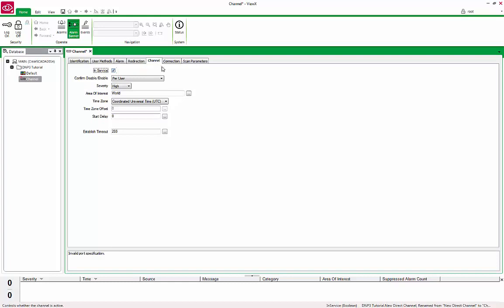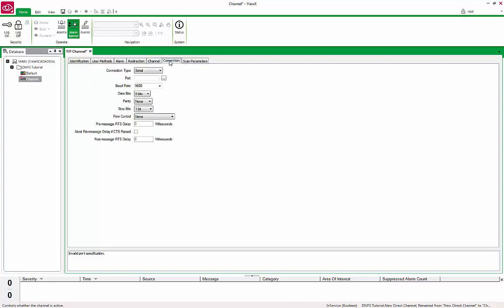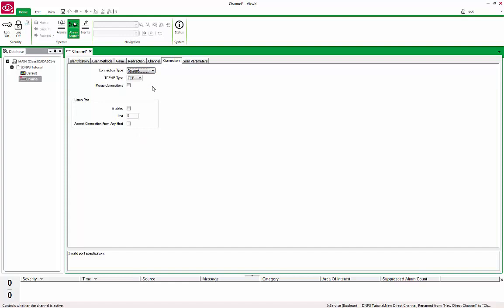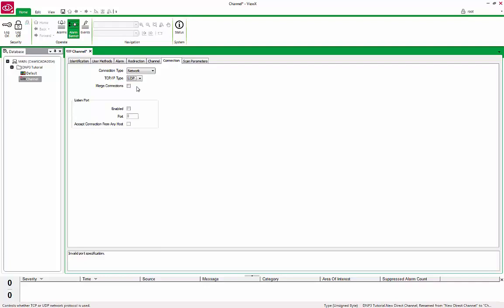Go to the Connection tab and change the Connection Type to Network and the TCP IP Type to UDP. You may need to change this part of the configuration depending on the setup of your DNP3 device. To allow your DNP3 device to send unsolicited message or report by exception, we can enable the Listen port and set it to 20,000.